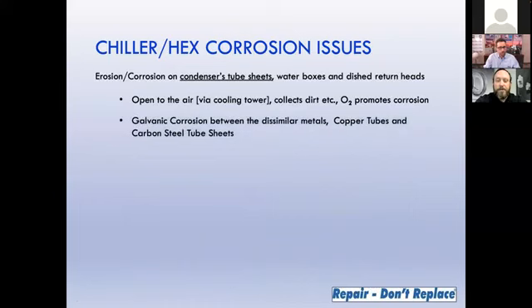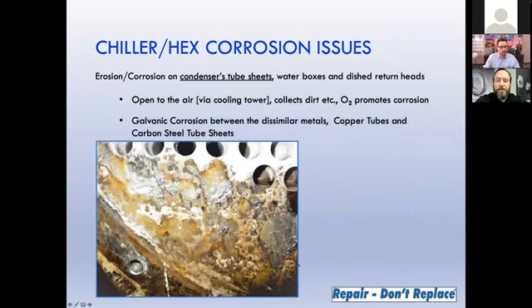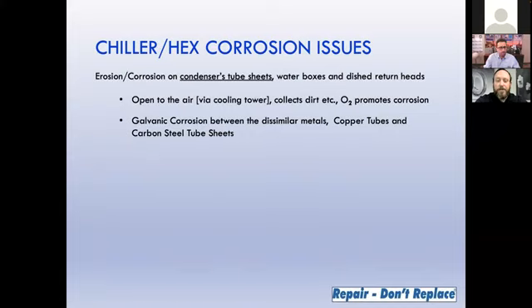Another type of corrosion that we often run into is galvanic corrosion, which is corrosion between the dissimilar metals of the copper tubes and the carbon steel tube sheet. As you can see in this photo, the corrosion is starting to form all over the tube sheet, but really pay special attention in between the tubes, where bimetallic corrosion is the most severe. Occasionally, the evaporator bundle is also treated, but they are usually on a closed loop system and much less prone to corrosion.